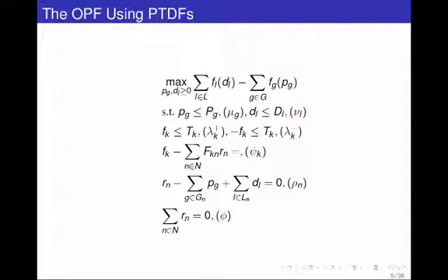And if you remember from last lecture, and this is kind of a detail, but maybe you've picked it up from the homework, this is a rank n-1 set of linear inequalities, where capital N is the number of buses in the system. Then we throw in this power conservation of energy constraint that makes it a full rank system, that makes this mapping of injections and flows a one-to-one mapping.